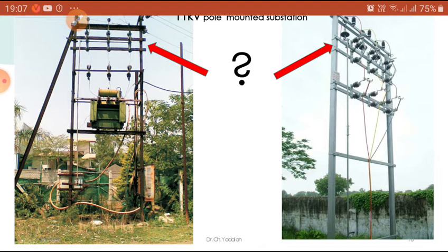It can be operated under low voltage, and it can be operated under load condition also. Whenever a load-carrying conductor is suddenly opened, there is a possibility that an arc appears. This arc can be quenched by using atmospheric air pressure. That is why we design male and female contacts for the AB switch terminals. At the time of manufacture itself, we decide the breaking and making contact capacity.